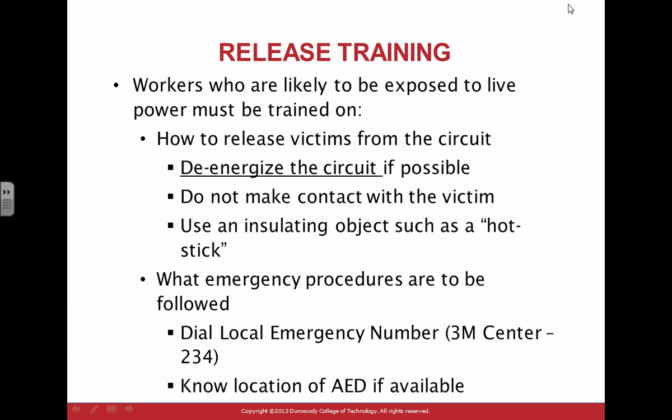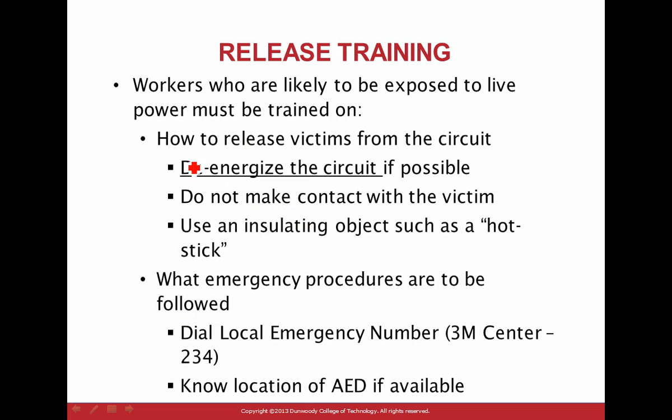Okay, let's talk a little bit, guys, about release training. Workers who are likely to be exposed to live power must be trained. Only the people who have to be exposed to live power, which you guys show in the surveys looks like all of you, working on exposed parts of more than 50 volts. So you have to be trained on the following: how to release victims from a circuit.